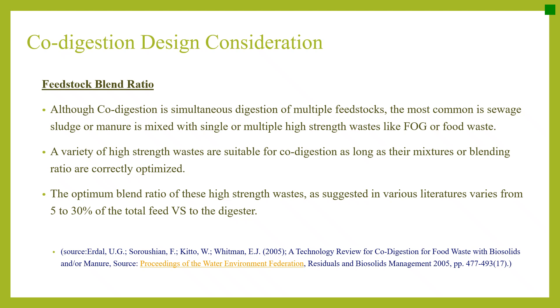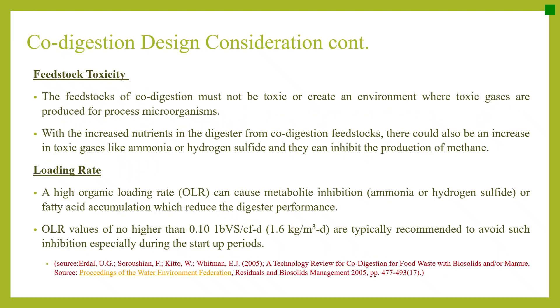If the blend ratio exceeds this, it may result in various process upsets due to product toxicity in later stages. The feedstocks of codigestion must not be toxic or create an environment where toxic gases are produced. With increased nutrients in the digester from codigestion feedstocks, there could also be an increase in toxic gases like ammonia or hydrogen sulfide, which can inhibit methane production. A high organic loading rate (OLR) can cause metabolite inhibition — ammonia, hydrogen sulfide, or fatty acid accumulation — which reduces digester performance.